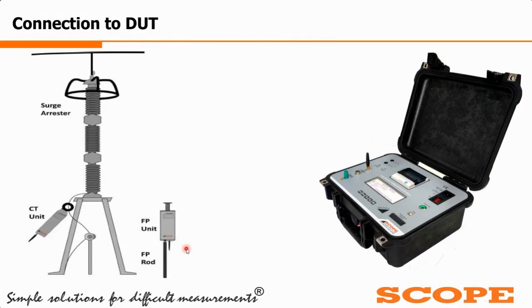Now, connection to the DUT is very simple. The LA you need not take offline, but for the measurement we need to take some precautions. The CT unit, as we can see over here, has to be connected in between the LA base and the earthing strip, but before the LA counter. We need to keep this CT unit there to get the proper result. If we take it after this, the result varies a lot. So you must be very careful to hang this CT unit in between the LA base plate and before the LA surge counter.